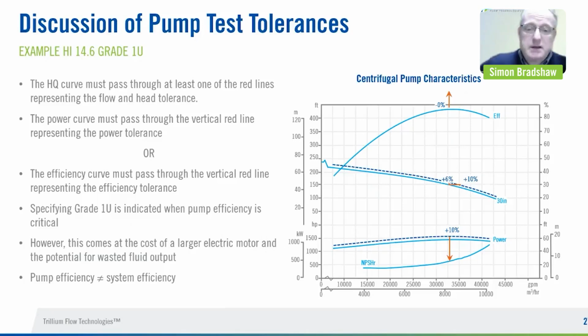And in this case, the setup of the allowable tolerances is quite different. So for the head and flow characteristic, you're only allowed a positive tolerance. So either up to plus 6% on head and up to 10% on flow. You are not allowed any negative tolerance on efficiency at all. So the efficiency that the pump demonstrates on test must be at least as good as what was sold, if not slightly better. And you say, well, that's great.